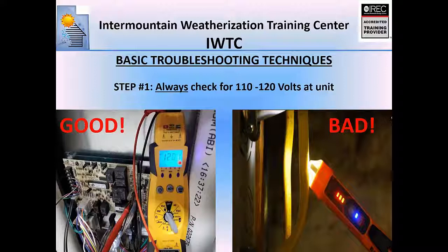Because you can have a problem with your neutral line, and this tester will still tell you that there's power there, but the furnace will not run, and the reading will be substantially different than 110 to 120 volts. So let's go ahead and take a look at that.